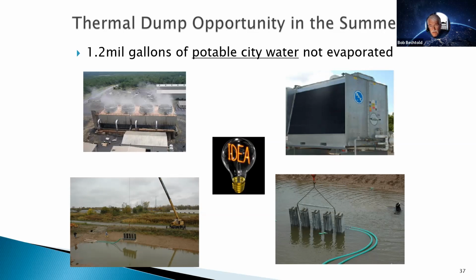We took some fin and tube heat exchangers, shown in the bottom right corner, sunk them to the bottom of our pond, and interrupted our process water loop, sending it to the bottom of the pond. That took out some of the heat in the water before it went to the cooling tower. Therefore, less energy and less water was needed to meet our water cooling requirements.